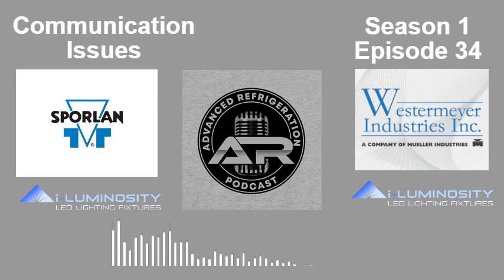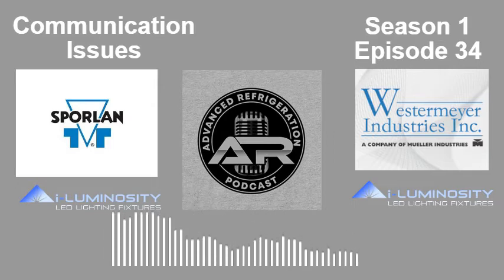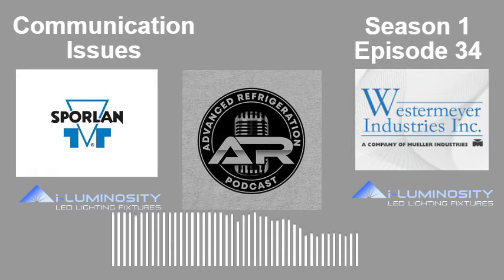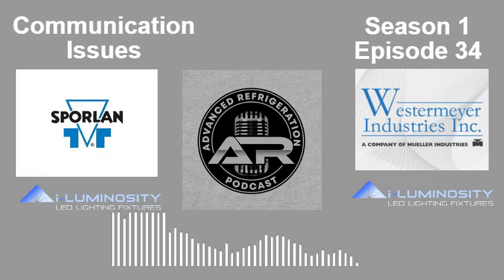Lastly, we have BACnet, which just about everything is going to right now. Walmart made a big push a couple years ago wanting everything BACnet. BACnet is what they call the engineer's protocol, a big building protocol for HVAC stuff. Just about everything can be BACnet. It's basically a group of points you can read and write to, a lot like Modbus.